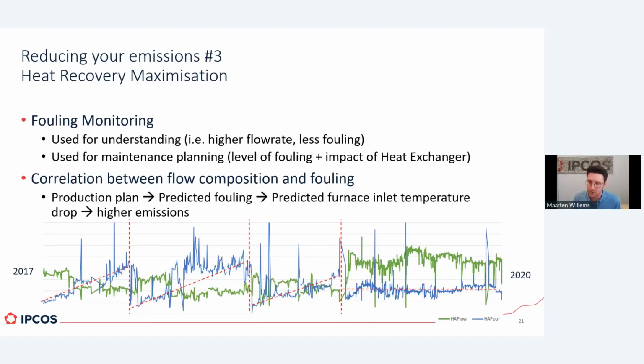At the bottom of the screen, you see this 3-year data that we have, and in blue you see the fouling over time. What you see is that the fouling actually increases, so your efficiency goes down up until the red line. The red line is actually your maintenance, so the fouling drops after your maintenance, increases again, drops, etc. Typically, this fouling is monitored once every month to once every 6 months.